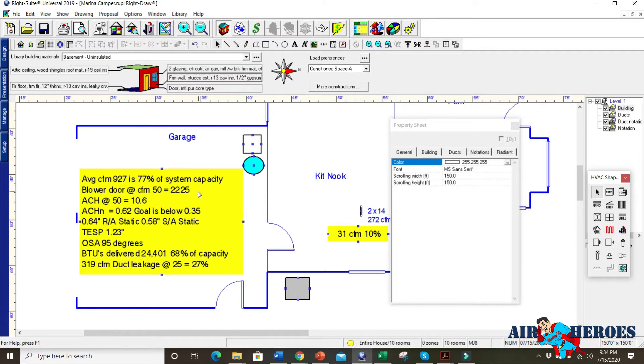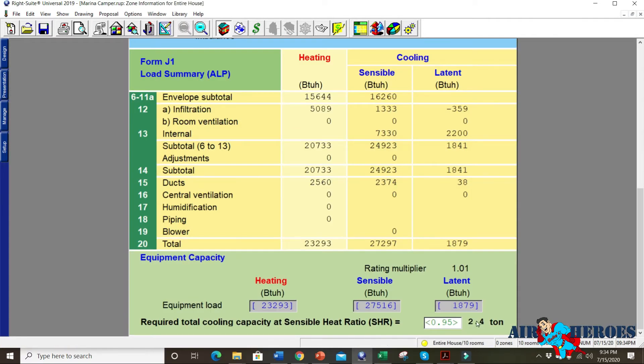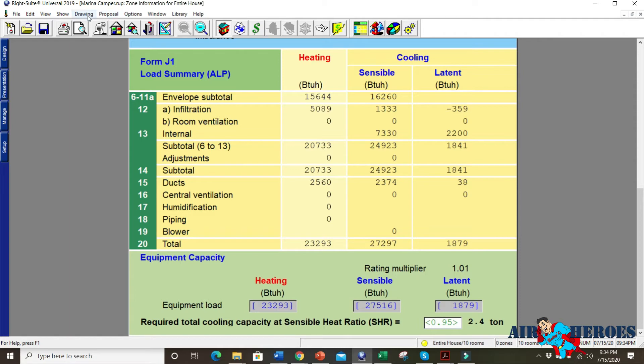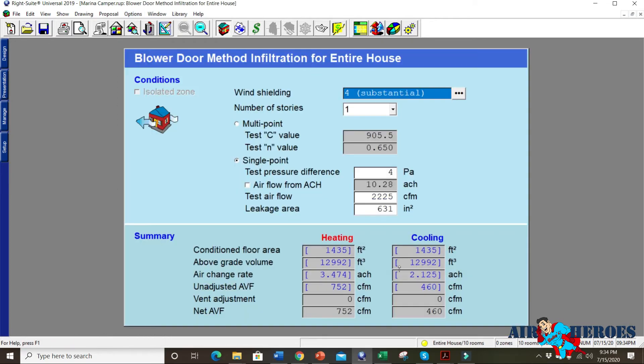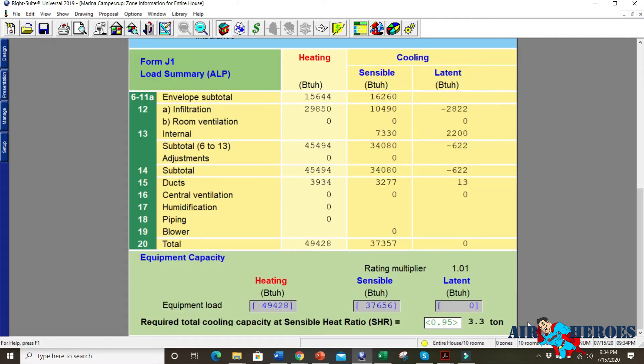We did a blower door test. The blower door test shows that if we use a simplified one, this house would take a 2.4, but these people had a bunch of can lights that were installed before they bought the house. And so if we change it to what we actually did when we do a blower door, we can actually do the infiltration method with the blower door. And we plug in what it was, which was 2225 CFM. Suddenly the unit, it needs a 3.3 ton unit. It went up a ton of cooling.